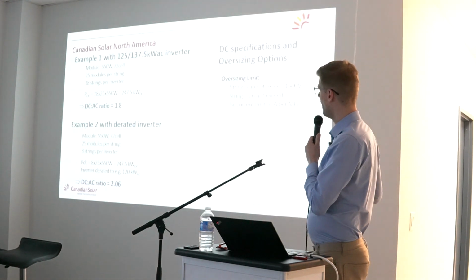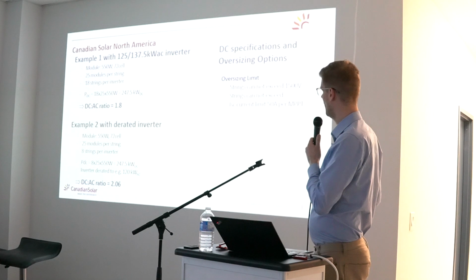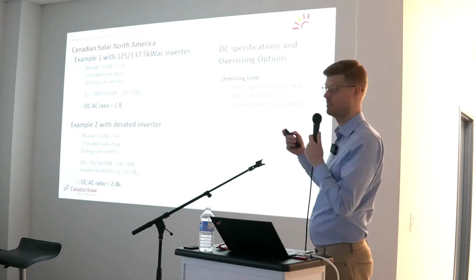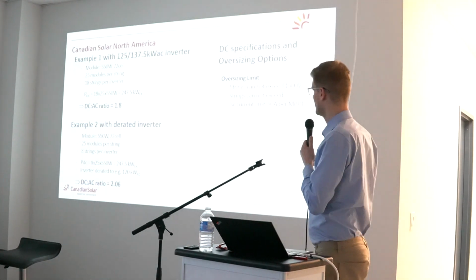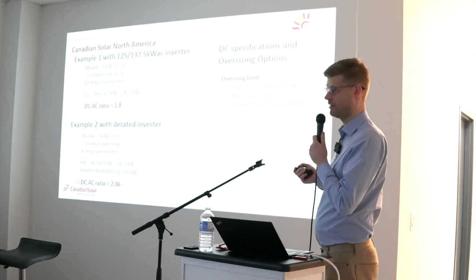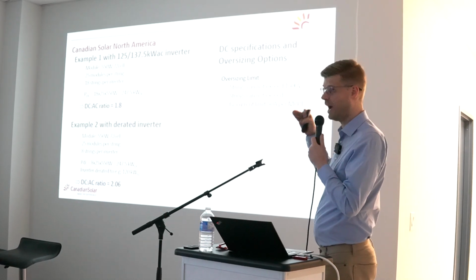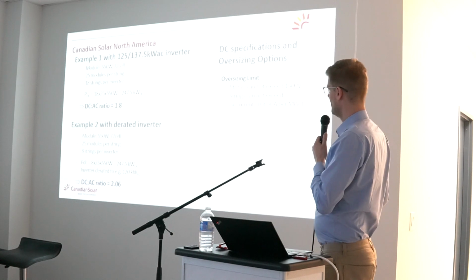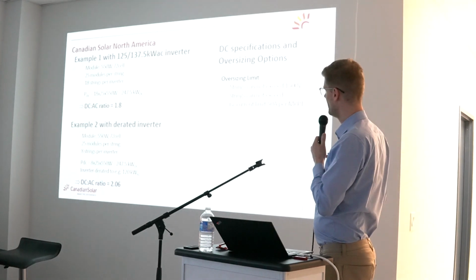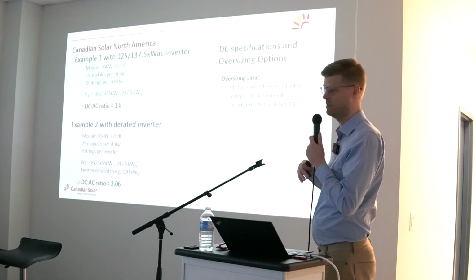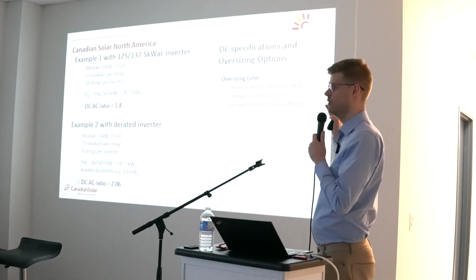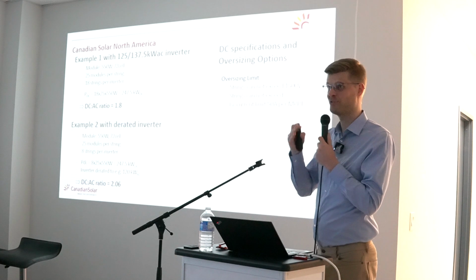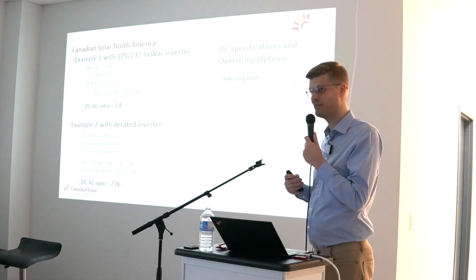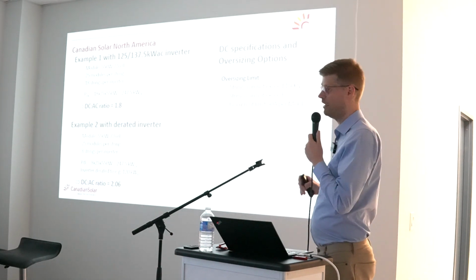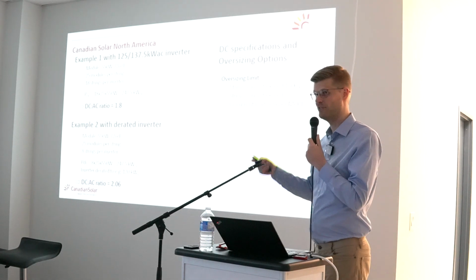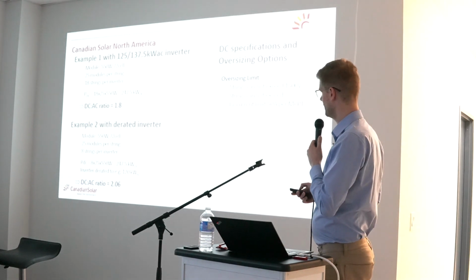The limits and the requirements, how far you can go, is very simple, similar to SMA, for example, or similar to other brands. You cannot exceed the 1,500 volt. That's obvious because it's a system that is up to 1,500 volts. The next part is, as I mentioned earlier, the 50 amps will give you enough capacity for pretty much any module these days, but you cannot exceed the 50. So 3 panels, for example, on a bifacial, even if you would have the fusing, would not work with that 50, with all the additional safety margins and the additional current.